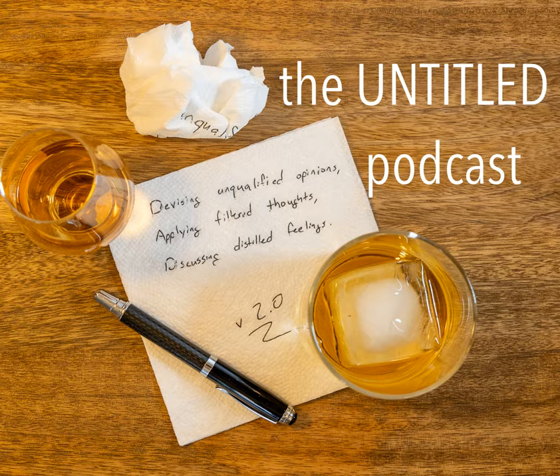All right, so let's back up ever so slightly. You have 8 conductors in a wire. 4 twisted pairs, yep. You can have issues with a couple of the pairs and not have a problem depending on what you're taking advantage of. But when you're talking about PoE to access points and higher bandwidth devices, having a problem with any pair can manifest itself in odd ways. And so with especially modern devices, you start to question cabling first and rule out other things second.